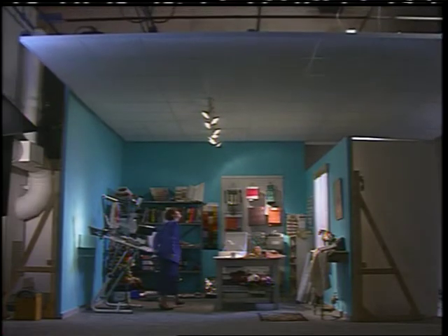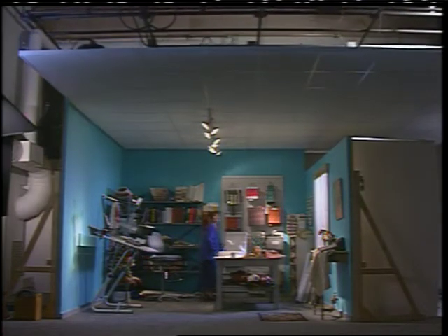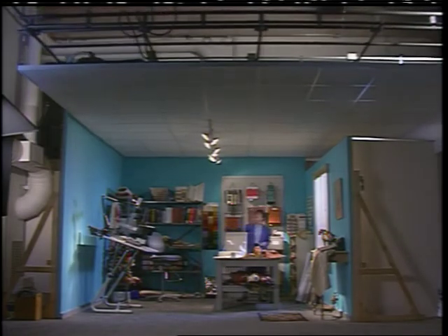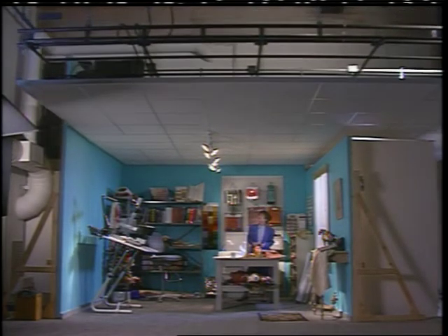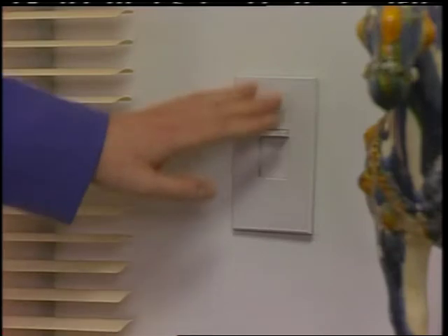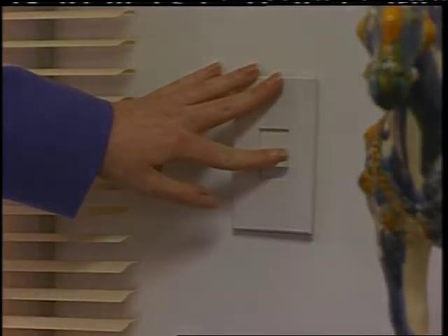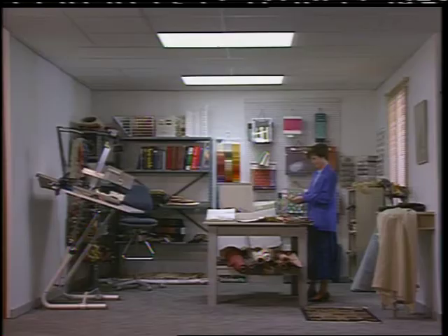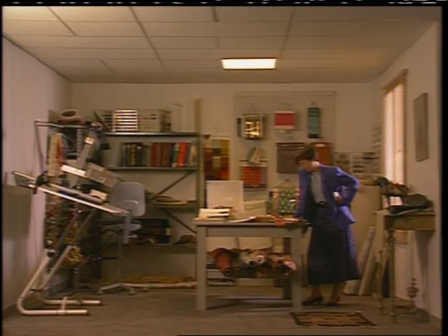By combining the benefits of room structural modifications, the upgraded luminaires, and the daylight controls, the energy efficiency of the lighting design for the studio has improved considerably. Each modification maintained the recommended 50-foot candle light level while allowing for a decrease in electricity consumption. Greater savings could be achieved by choosing luminaires with even higher lumen per watt ratios.